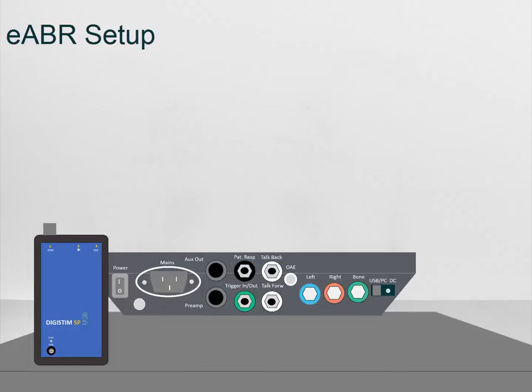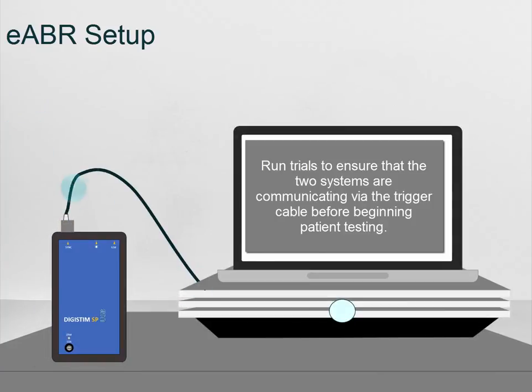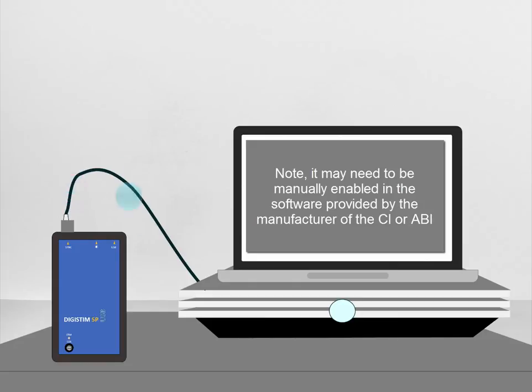With the correct cable selected, insert this into the labelled trigger port on the back of the Eclipse. The other end should be connected to the cochlear implant stimulator system. Run trials to ensure that the two systems are communicating via the trigger cable before beginning patient testing. Note, the stimulator may need to be manually enabled in the software provided by the manufacturer of the cochlear implant or the auditory brainstem implant.